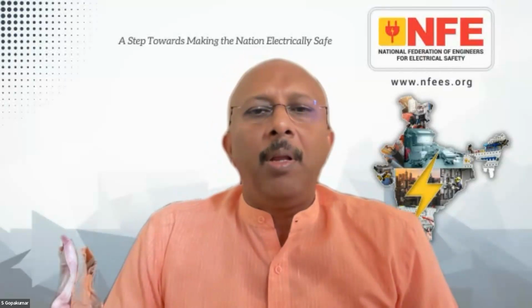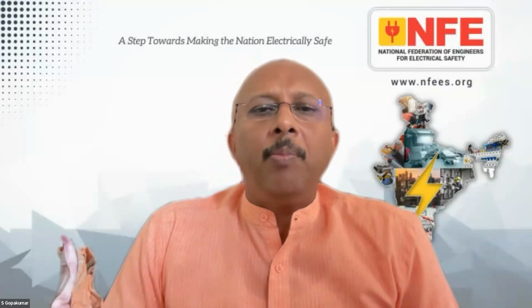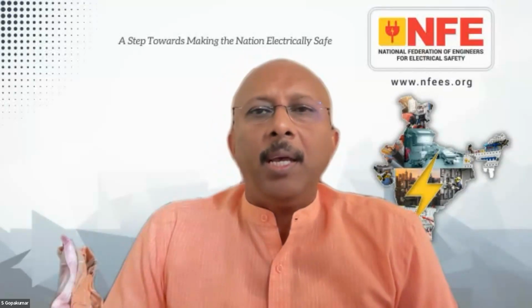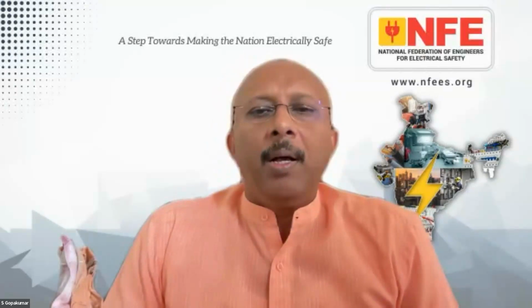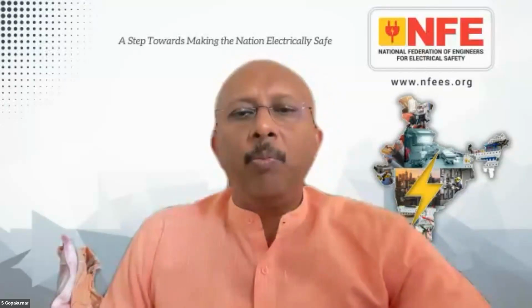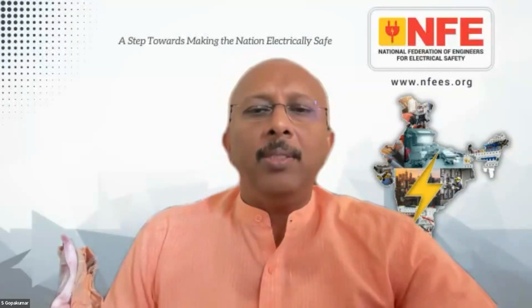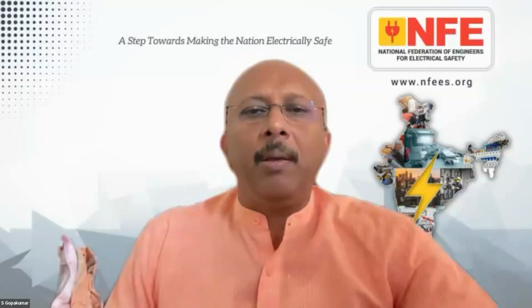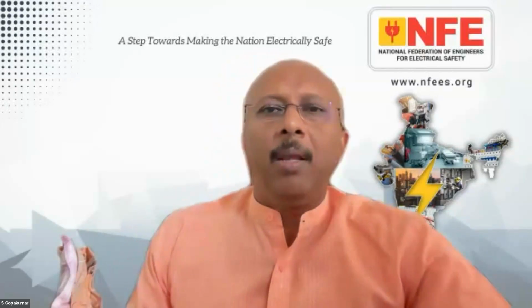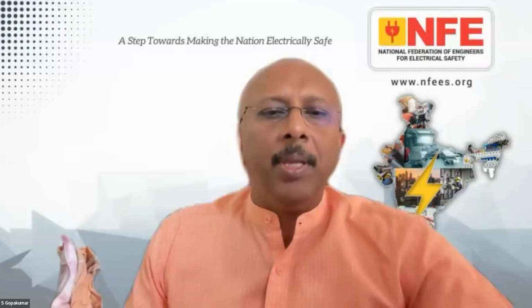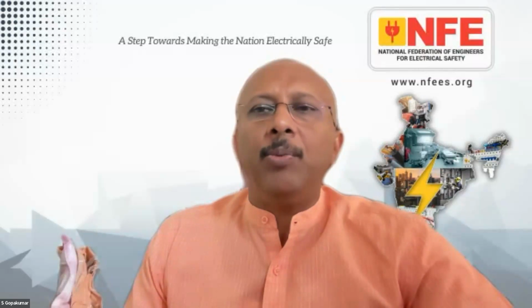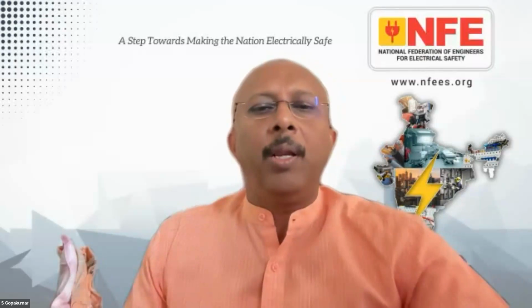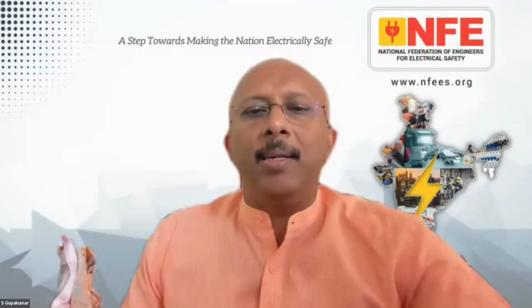For example, one of the protective measures is that if the leakage current is more than 10 milliampere, the equipment manufacturer should put two earth terminals in his panel. So two separate earth terminals will be there. One of the earth terminals is the place where the leakage current is coming, and that part has to be connected to MET through an insulated conductor. These are there in the standard. They are already doing it.